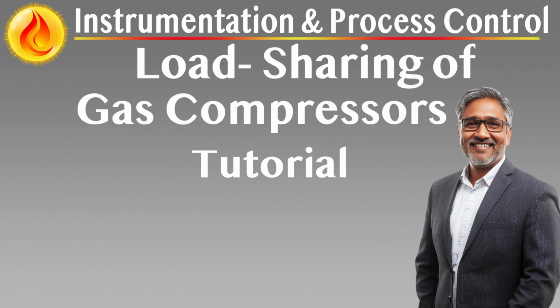This approach is ideal for handling sustained or long-duration recycling, where using only hot recycle lines could lead to undesirable heat buildup and energy loss. Cold recycle control activates early in the surge risk curve, providing a proactive and energy-efficient method to protect the entire compressor train from surge while minimizing thermal stress.